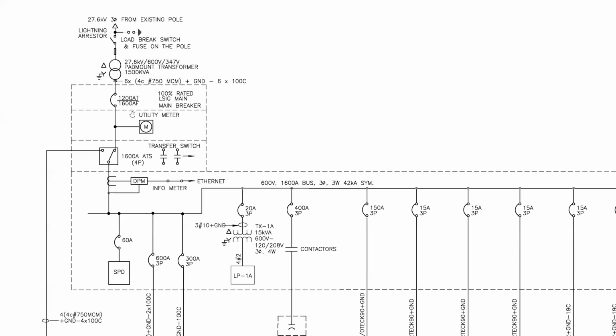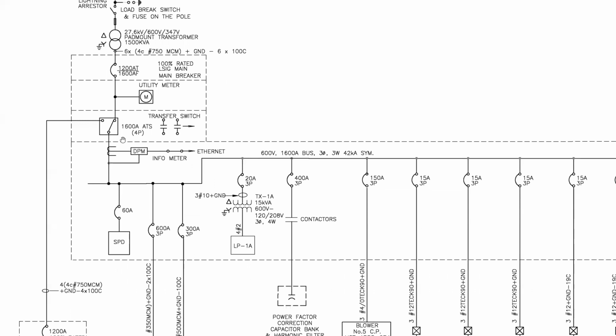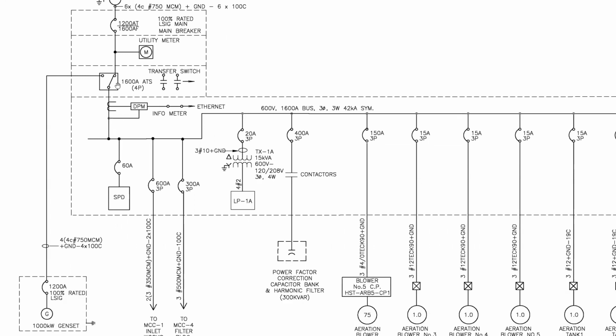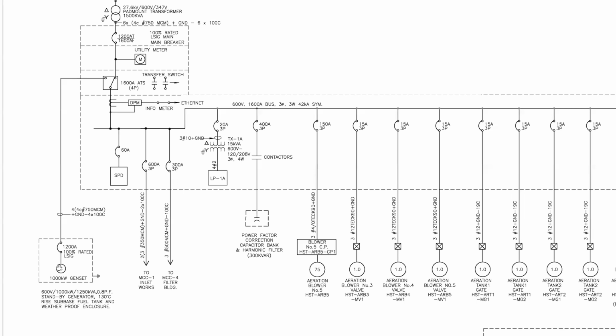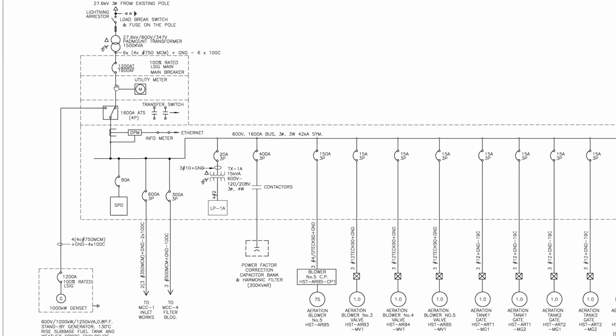This is a 1200 AT main breaker. This big one, utility meter. This is an ATS, so an automatic transfer switch for the facility. This transfer switch is connected to a 1,000 kilowatt diesel generator. So when normal hydro's on, you'll have power come into the plant. When power fails from hydro, this generator will turn on, come into the ATS. The ATS, this contact will actually switch over and then provide power. There are dozens of connections inside of the ATS, but on this drawing, we don't care. We just need to know that there's an ATS, there's some transfer information, and the additional wiring for that, for faulting, for tripping, for what position it's in, that would be found elsewhere.